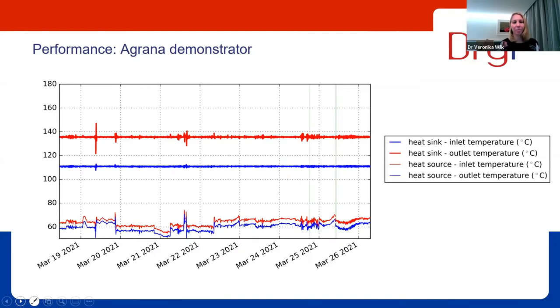This is a time series from the Agrana installation, a week of operation in March this year, and in the lower part of the diagram, we have the heat source temperature. In red is the temperature coming to the heat pump, and the blue line indicates the temperature reduction with the heat pump. We see that the heat source is ranging between 60 and 70 degrees C, and we see quite a lot of fluctuations there. In the upper part of the diagram, we have here the heat supply side. So this is the inlet temperature, and at that time the heat pump was operated at 135 degrees C. And we see here in a very nice way that the process control of the heat pump works fine. So it levels out the fluctuation that are coming from the heat source.